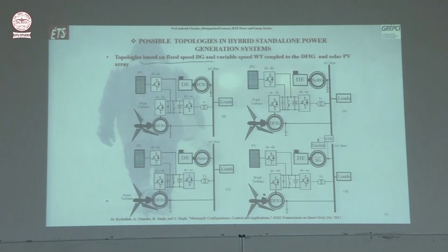Topology is based on fixed speed diesel generator, variable speed wind turbine coupled to DFIG, and solar PV array. So you see, this is the wind turbine, doubly fed induction generator. Rotor side you have an AC to DC converter of 1/3 capacity. Then this is the DC bus where you have a battery bank and dump load, and the size of this inverter will increase because PV power is also coming on DC. So this power will be transferred here. PV power goes through a DC to DC converter for MPPT, and this power comes to the DC bus. The size of this inverter will increase because this power plus this power is going, and this is the fixed speed diesel generator.